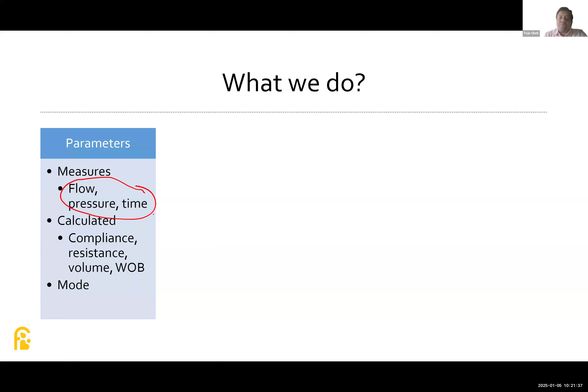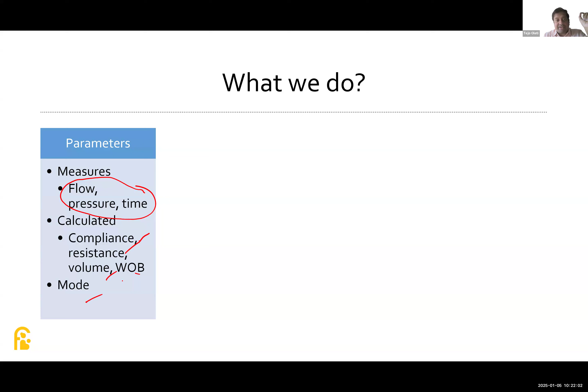All the other things like volume and any other parameters that you are seeing, like minute ventilation and other things, are just extrapolated from these three basic parameters. So the machine also calculates the compliance based on this resistance and the volume that is generated. And of course, we look at the work of breathing manually, clinically also. The machine also tells you whether the mode that you have kept is working or not.